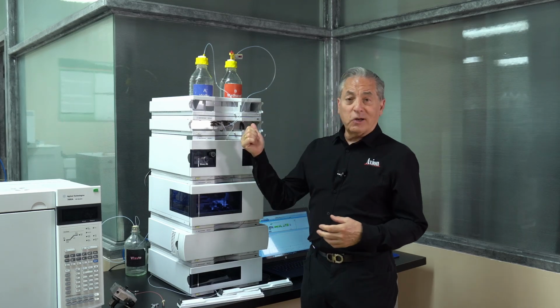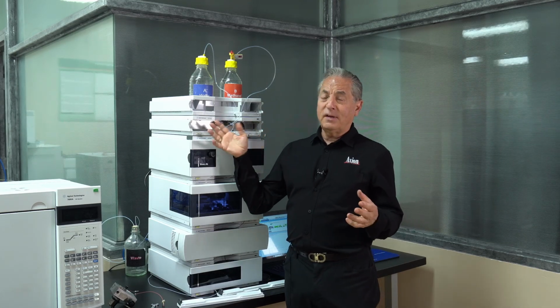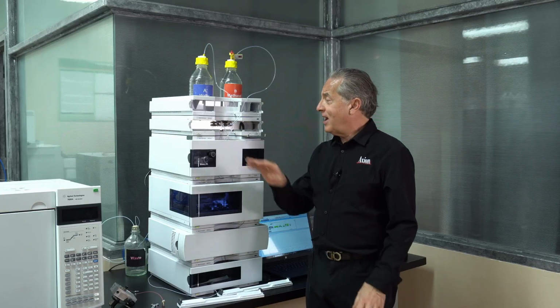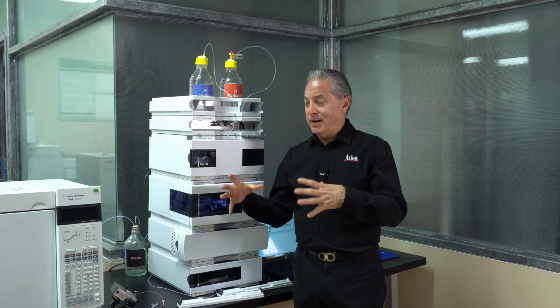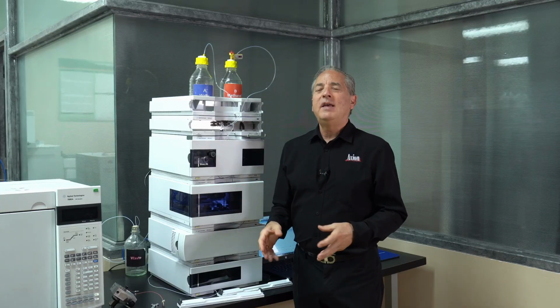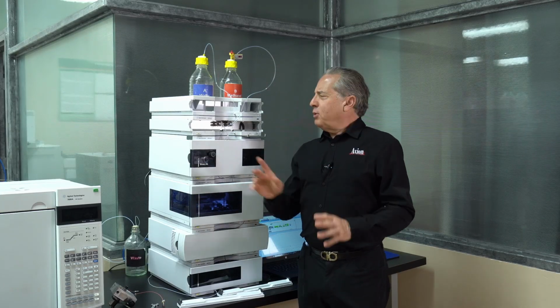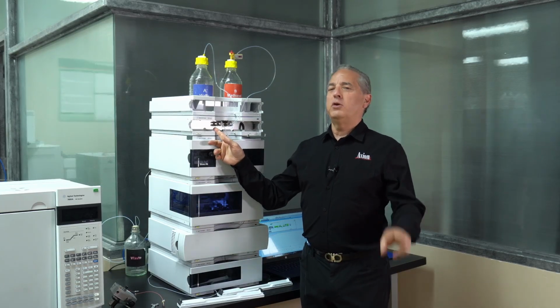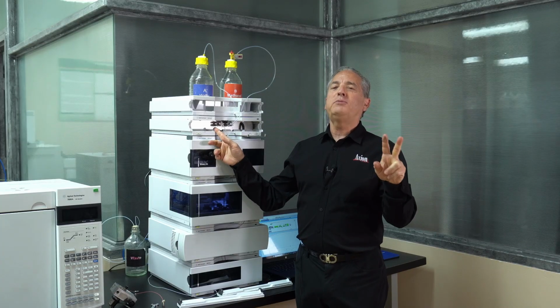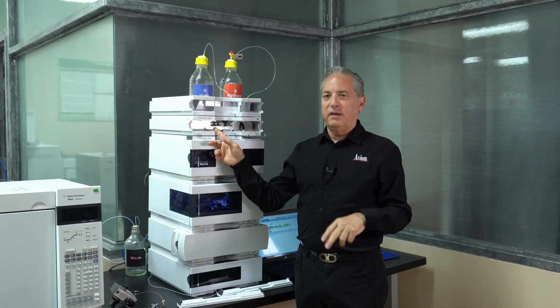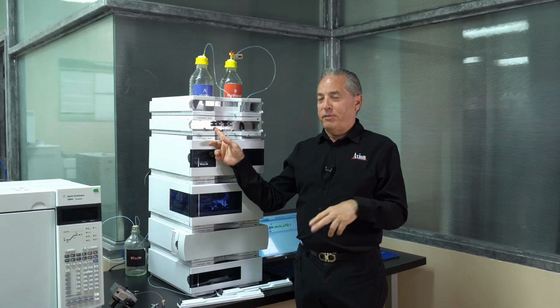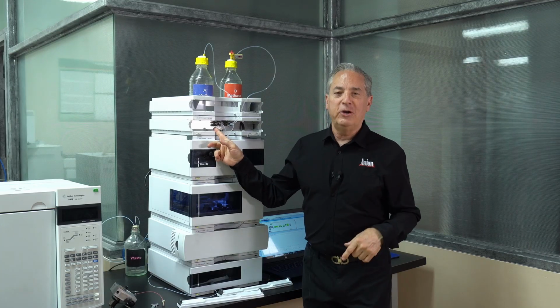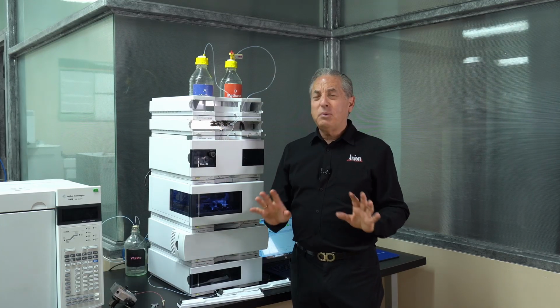So if you call up Axion or Waters, and say, hey, I precipitated buffer in one of the tubes, they're going to say, I've got bad news for you. That entire vacuum chamber is one part, and you're going to buy the whole thing, and it's really expensive. So if you plug up channel A, let's face it, we only use 2 channels. We only use A and B. So if you plug up A, then switch to B and C. If you plug up B, switch to C and D. If you plug up C, shame on you, then you have to get a new degasser. Best answer, don't plug up the channels.